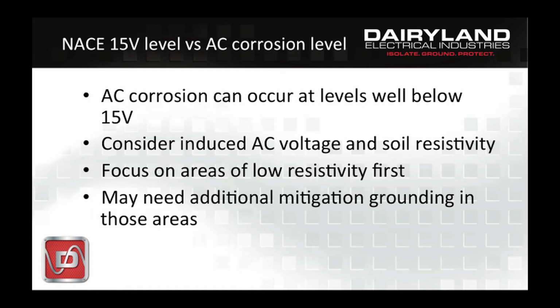So, in conclusion, AC corrosion can occur at levels well below 15 volts. It can occur at even only several volts. So you have to look at the AC voltage on the pipe, even after mitigation, and the soil resistivity. The key here is it's the low soil resistivity areas that are the concern, and they will have the corrosion risk. You're not going to have a problem with high soil resistivity areas. So if you must concentrate your efforts and your maintenance dollars somewhere, focus on the low resistivity areas. The result will be, if you put in additional mitigation grounding, that would reduce the induced voltage further.